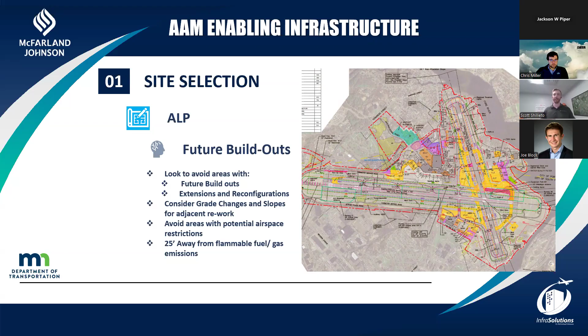Another thing per NEC is 25 feet away from flammable fuel or gas emissions. So don't just think about aircraft Jet A or avgas locations, but also natural gas or anything like that coming into a building - you need a 25-foot separation. That's per NEC, but your AHJ and fire marshal may go above and beyond that. I've had some say 50 feet, others say 100 feet. It varies, and it's something you can work with your permitting agent on to understand what will make them feel safe. And remember, that's measured from the end of the cord to where the flammable gas is coming out - so if you have a 50-foot cord for the charger, imagine that fully extended, plus a 25-foot separation.